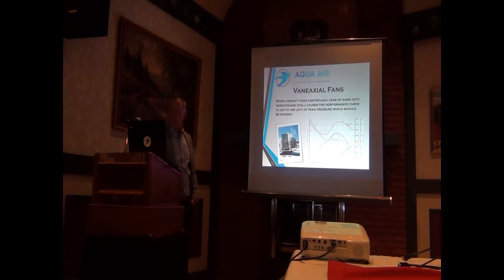Not much difference in the fan curve from the tube axial. Same thing, they have overloading characteristics. So again, you don't want to be on the right hand side of that. You can have an overload situation. Here, it looks like they're using them for an exhaust fan application. Aerodynamic stall causes the performance curve to dip to the left of peak pressure, which should be avoided. So that's what we're talking about with the fan curve.